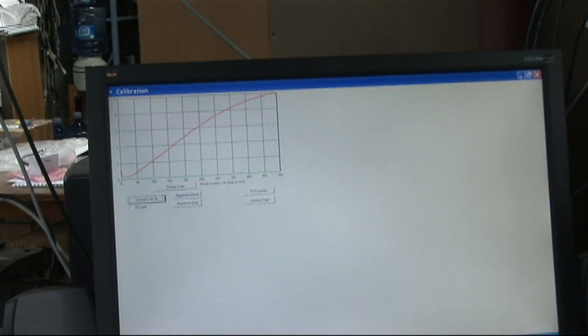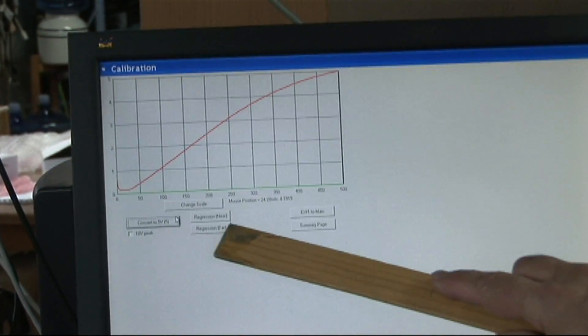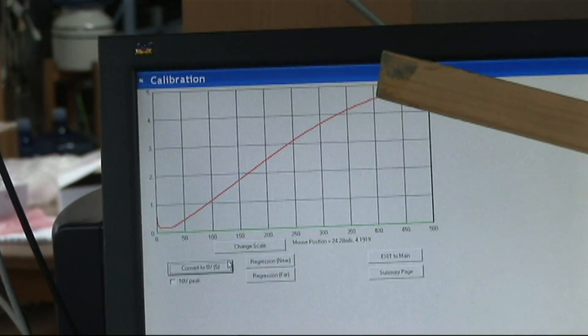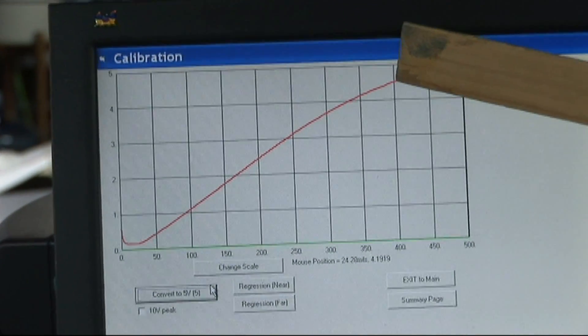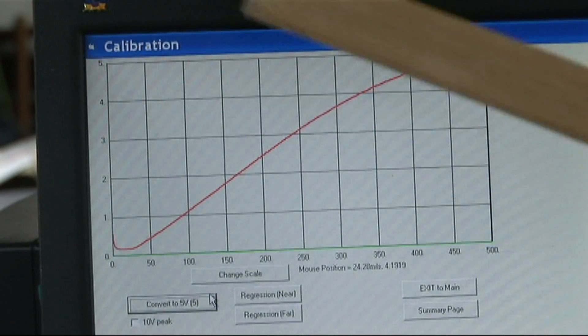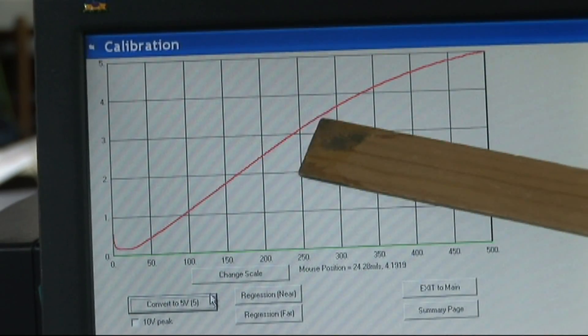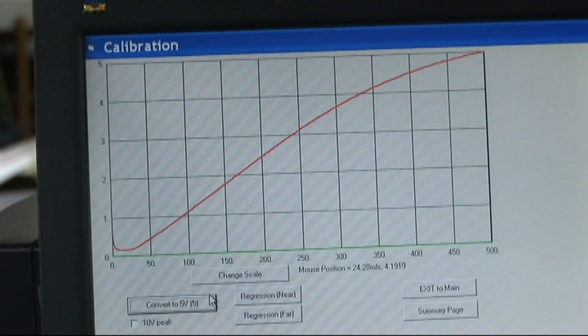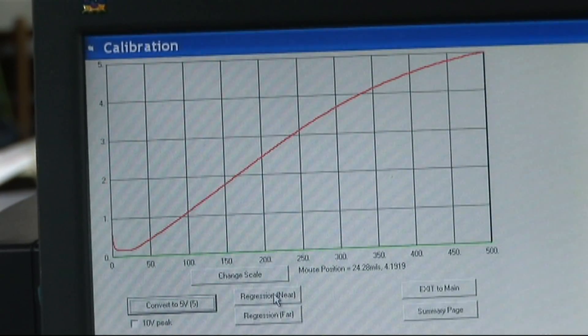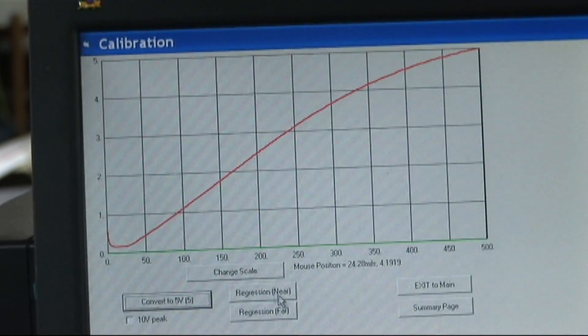Which again, if you look over here to the left, now this is the calibration chart, which we provided. So depending on the motion of your pin, if you start at a large distance and the pin approaches the sensor, then you'll be dropping down in voltage as the gap gets closer. So we've provided a linear operating range. But from what I know, your sensors are going to be using pretty much the entire operating range, almost a whole half inch.